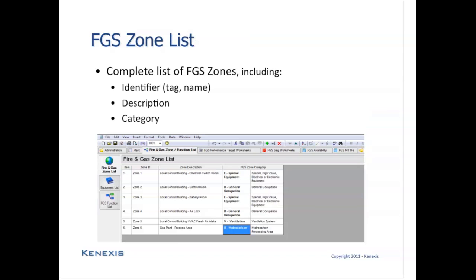The result of the fire and gas zone definition is going to be an FGS zone list, as you can see in the example below. The complete list of FGS zones for a facility will be created during this task, and for each item, you're going to identify what the zone is, typically some sort of tag number that defines the zone. You will describe the zone to give a little bit more verbal description and context for where the zone is located and what the zone contains. Next, you will define the category for the zone along with some of the attributes that caused you to select that zone type for the zone under study.